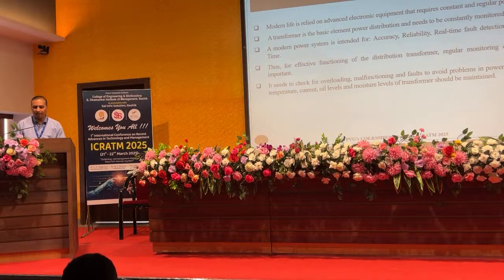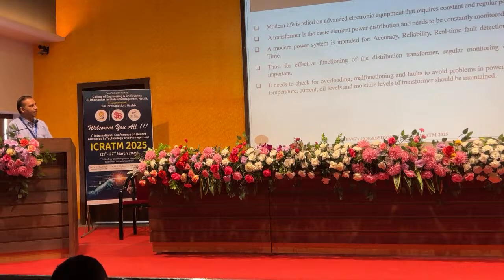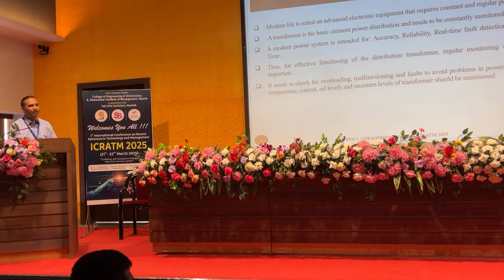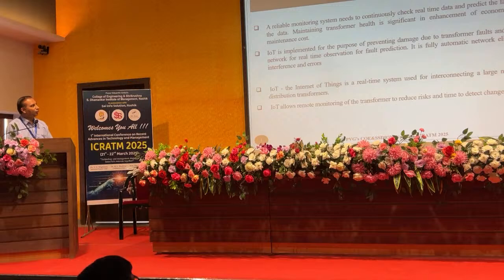What is the basic drawback of our existing system is they are having problems of overloading, malfunctioning and faults. Overloading is a basic mechanism that we are facing today everywhere. That is the reason the failure of the power is the main factor, is the overloading. So in this model we are proposing to determine various parameters like temperature, current, oil levels and moisture levels so that the transformer can be maintained accordingly. We need to continuously check the real-time data and can predict the fault by analyzing the data.